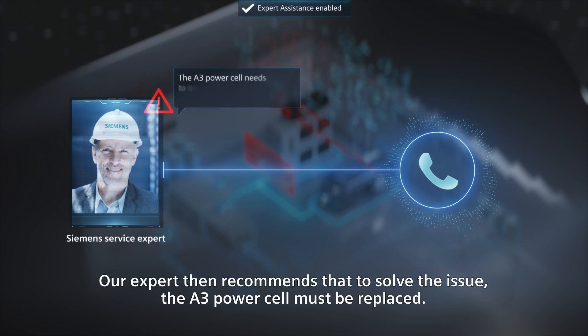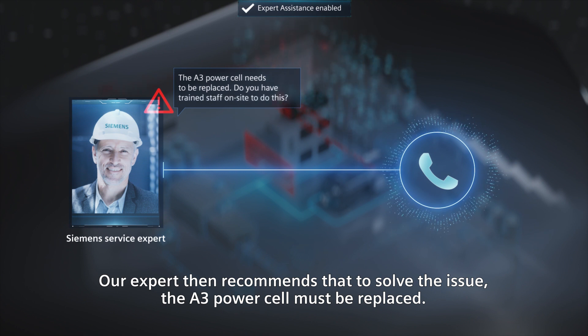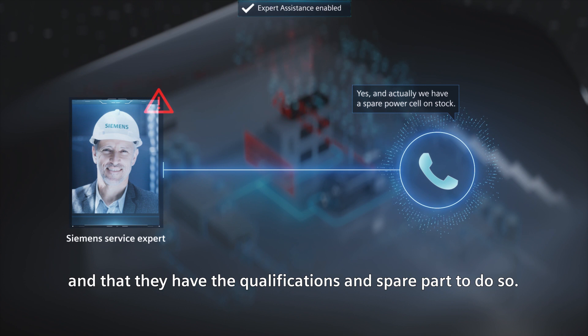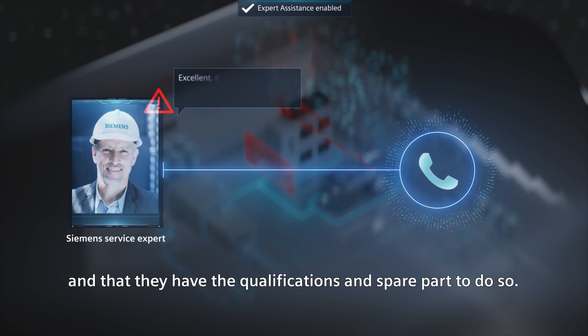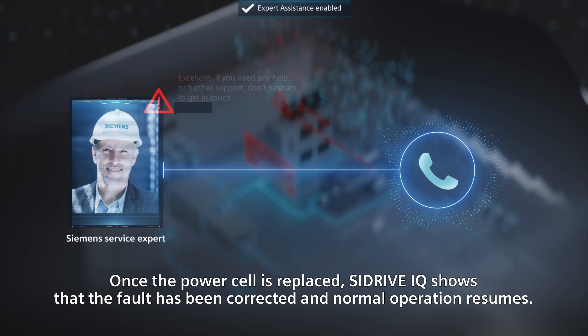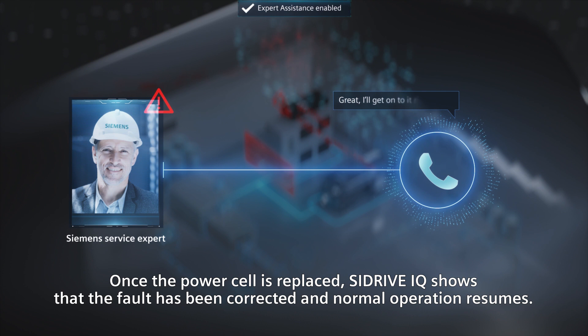Our expert then recommends that to solve the issue, the A3 power cell must be replaced. The operator confirms that they will do the replacement themselves and that they have the qualifications and spare part to do so. Once the power cell is replaced, SIDRIVE IQ shows that the fault has been corrected and normal operation resumes.